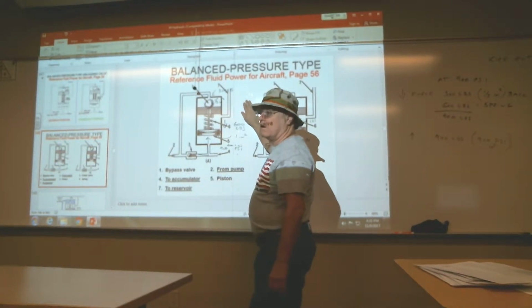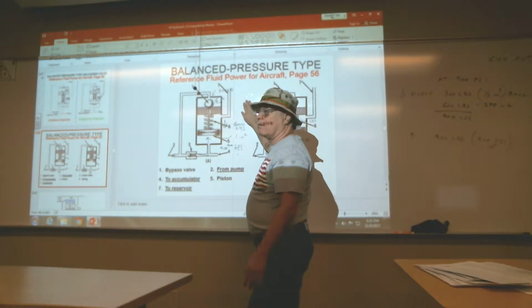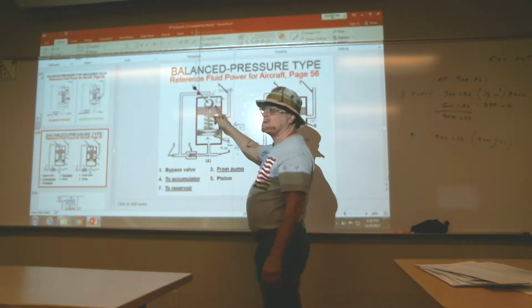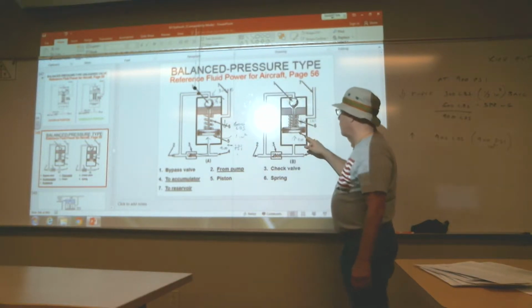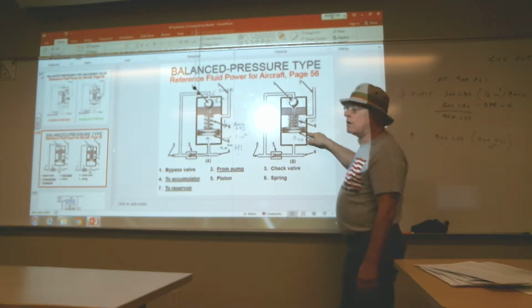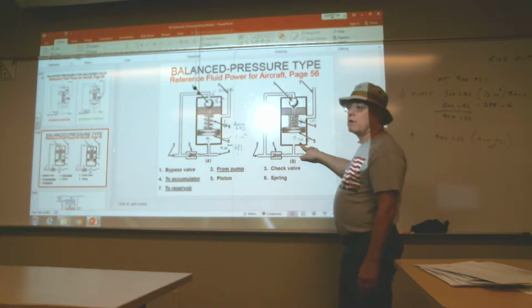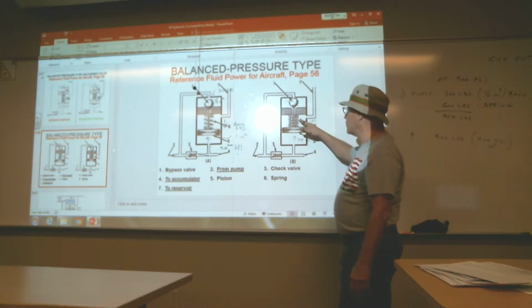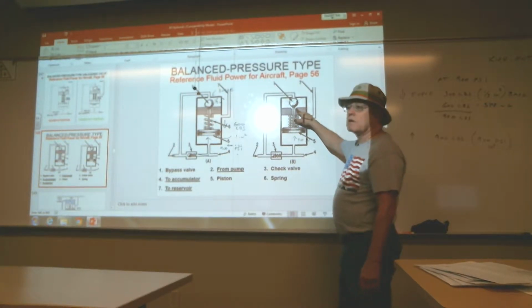So that's kind of like the tipping point. You get to 900 PSI, and then at 901 the ball is lifted off of the seat. At that point, the only thing keeping the piston elevated is really the pressure beneath the piston against a 600-pound spring. Then the pressure would have to recede to about 600 PSI before the ball recedes again.